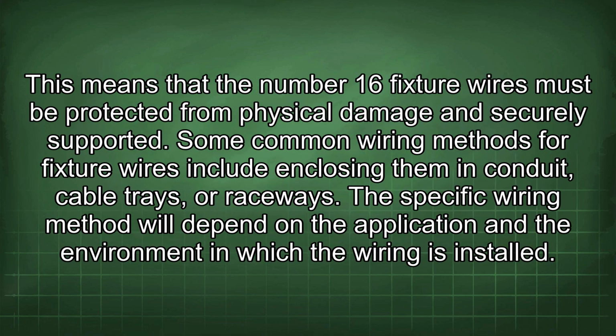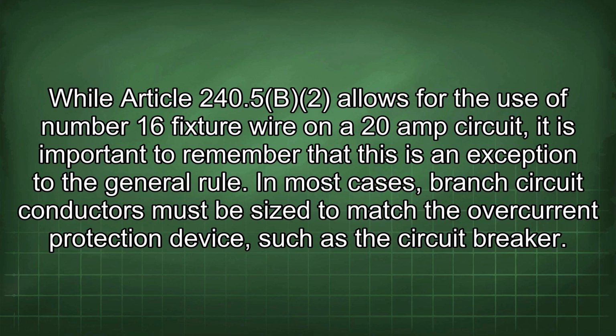This means that the number 16 fixture wires must be protected from physical damage and securely supported. Some common wiring methods for fixture wires include enclosing them in conduit, cable trays, or raceways. The specific wiring method will depend on the application and the environment in which the wiring is installed. While Article 240.5(B)(2) allows for the use of number 16 fixture wire on a 20 amp circuit, it is important to remember that this is an exception to the general rule.